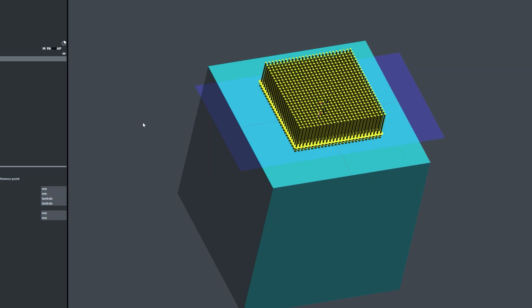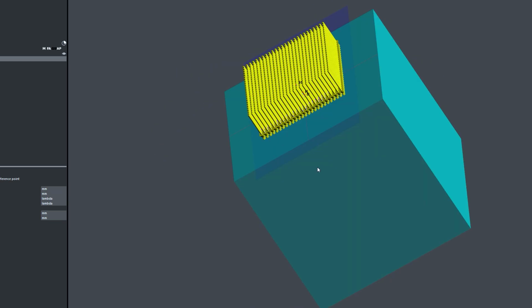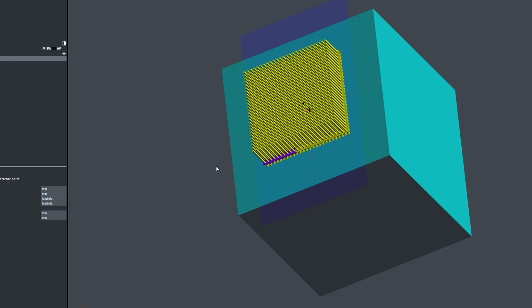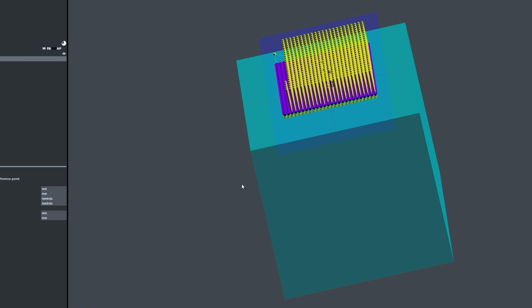The APD scan is a planar scan measured at 1 mm from the phantom surface, with the probe tip being just 200 micrometers from the phantom surface. Towards the end of the scan, a vertical Z scan is used to measure the field decay at the peak location. The measured field and its decay are used to compute the APD values at the phantom surface.